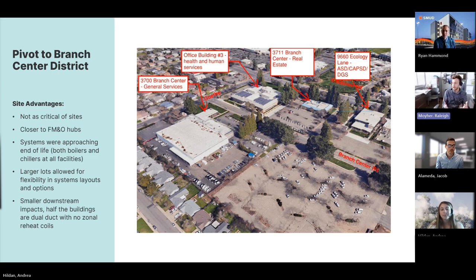That made it a much more attractive place to look at. On top of that, we had smaller downstream impacts. Half the buildings on these facilities weren't served with integrated piping that potentially needed to upsize. A lot of them are dual duct facilities with large air handlers on roofs delivering hot air into the building, so if we had to upsize hot water coils or swap out piping, it's exterior to the building and somewhat less invasive.